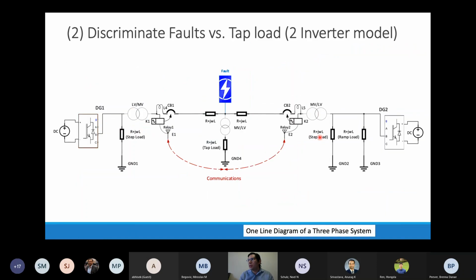So I'm passing to the next part. I want to show how this model works, so how we discriminate faults versus a tap load. Basically, we have in our case a two-bus system with two inverters. We have an inverter and its load, and on the other end of the line, we have another inverter and two different loads. And we know that thanks to our loop control, we will be able to share the load between them, how much they need to give to the grid.